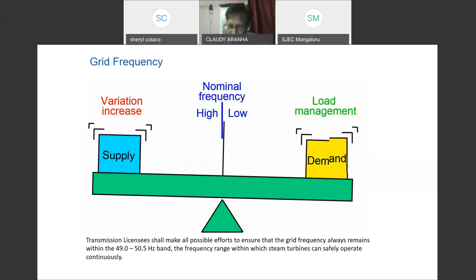Grid frequency. As per the grid code, the utility is supposed to maintain the grid frequency, because if the frequency comes down less than 50 cycles, there is heating and vibration, or more than 50 cycles, again vibration. This is harmful for generators, harmful for motors. It has to be maintained within the limit of the 49 to 50.5 band. If it is more than that, then there will be a disturbance or a lockout, shutdown, blackout will happen, causing the collapse of the grid.